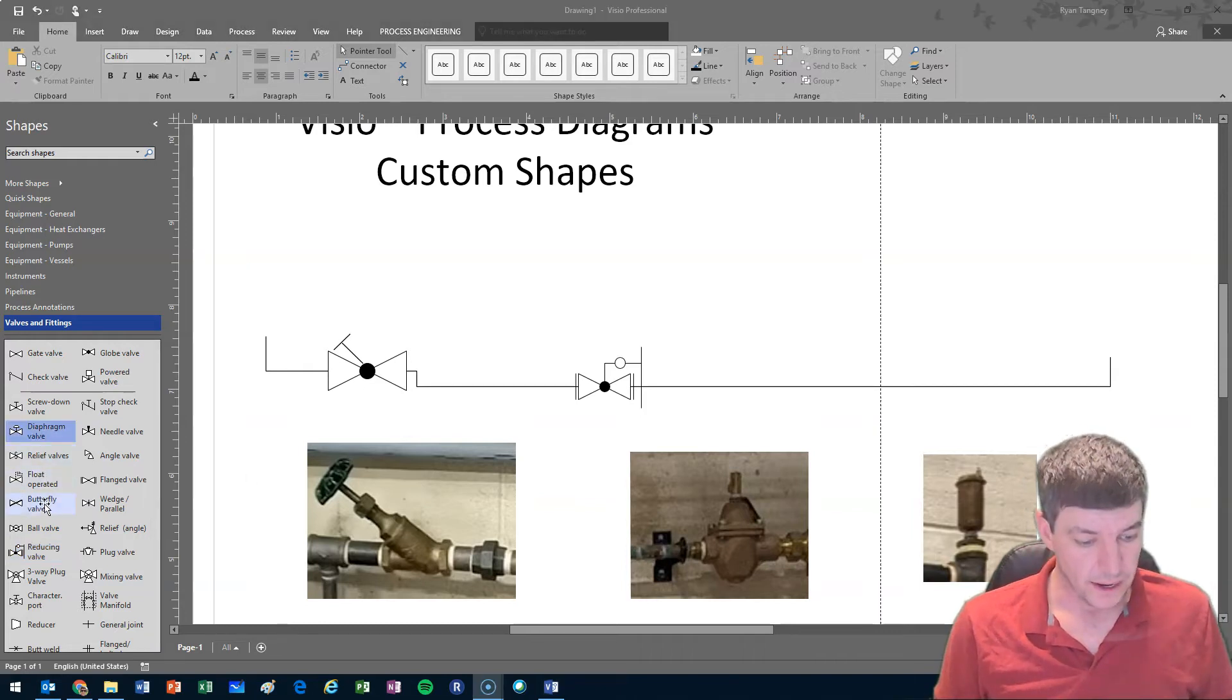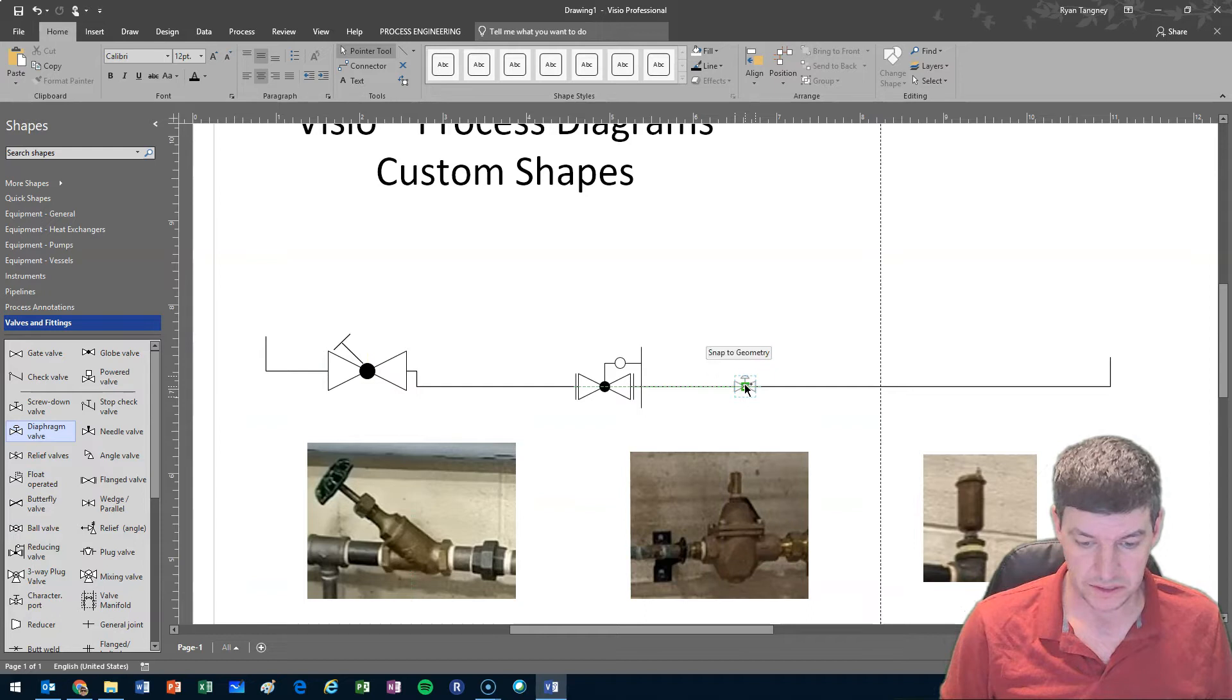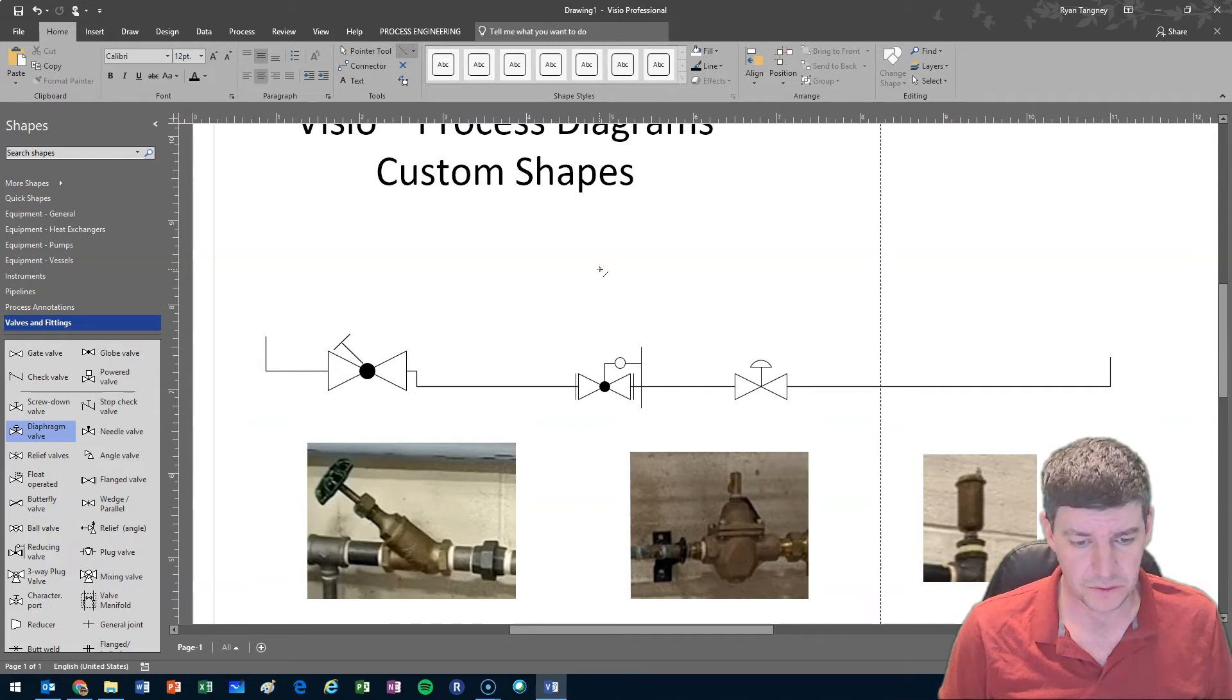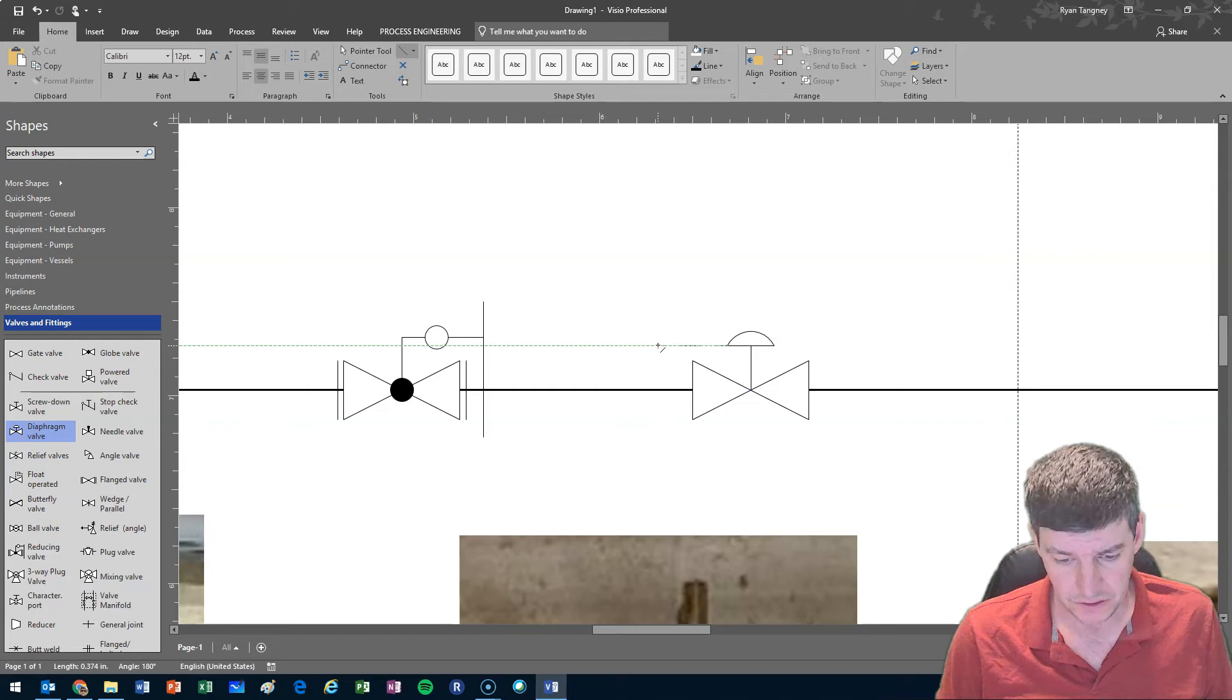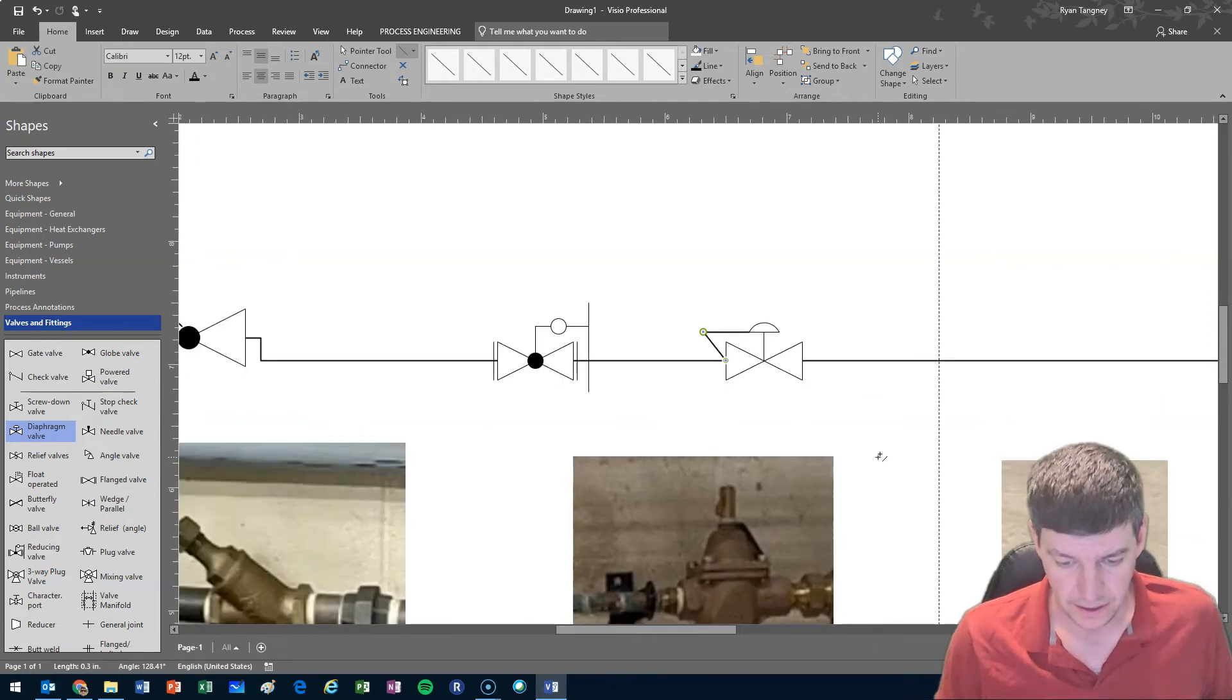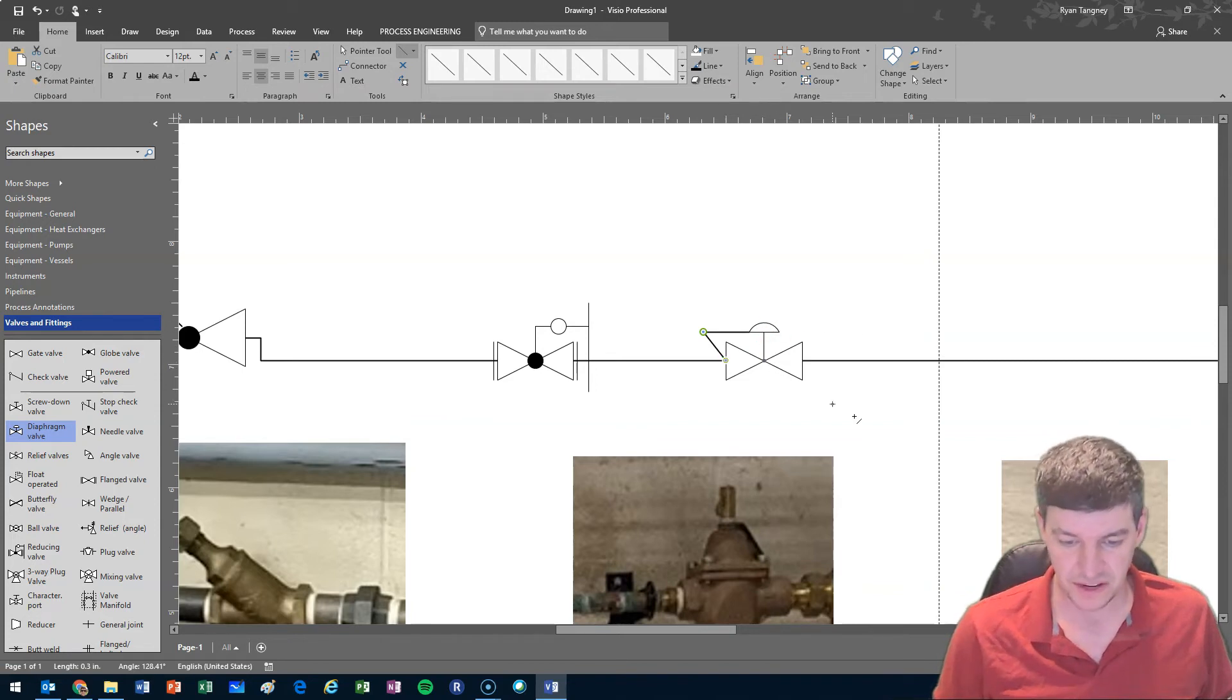So maybe what I'll do is start with a diaphragm valve. I'm going to put this into place and increase them in size. Once again I'm going to use my line tool and modify this drawing for this symbol. So I'll pull off of the top and go straight across, create a line and then draw a line from here to here and that indicates to me that I have a control valve that is reading the line pressure downstream of the valve and will adjust the valve position.